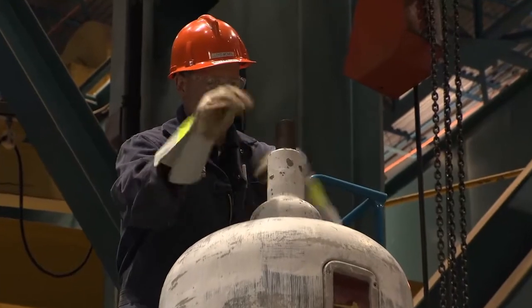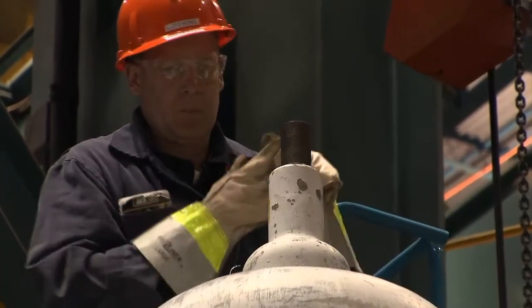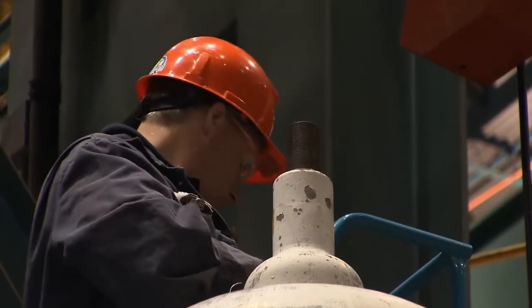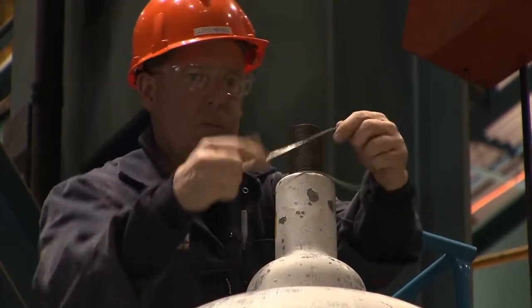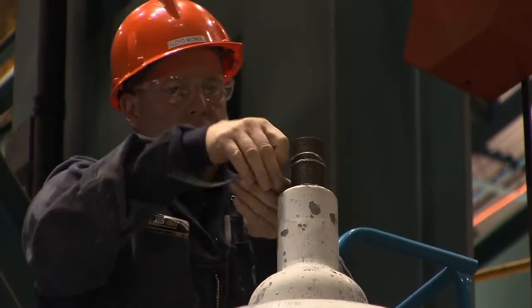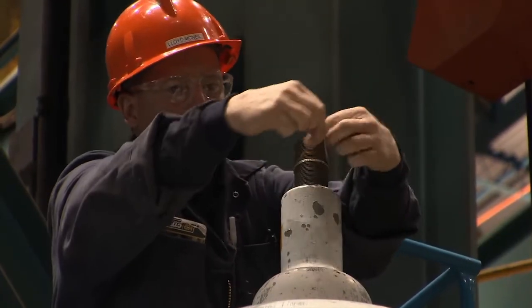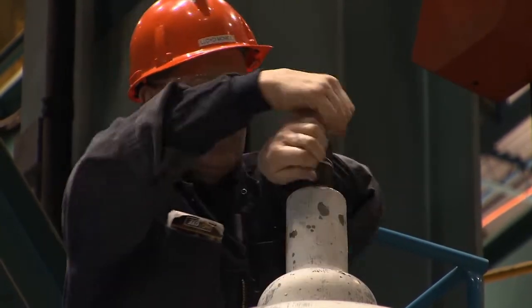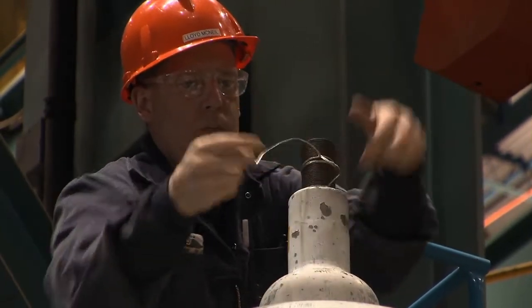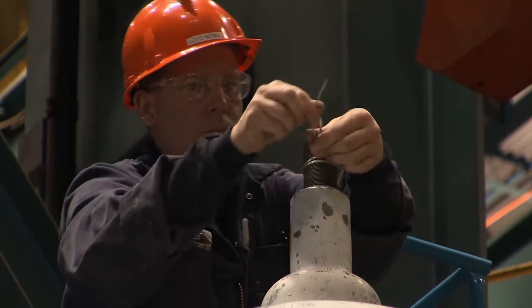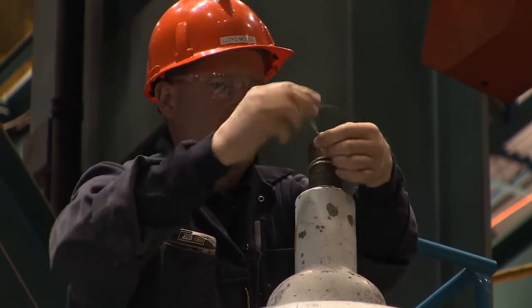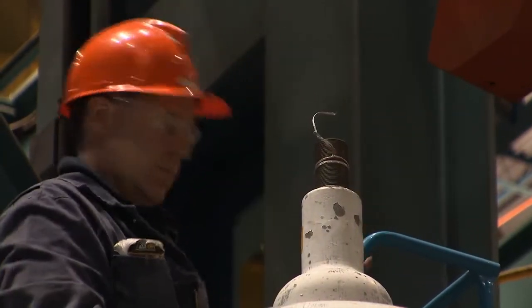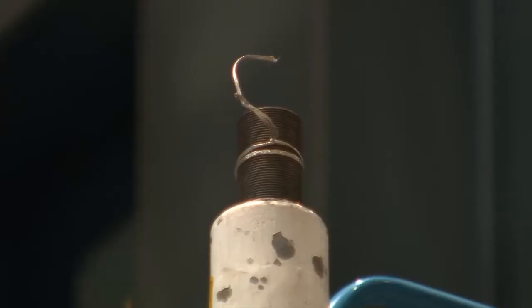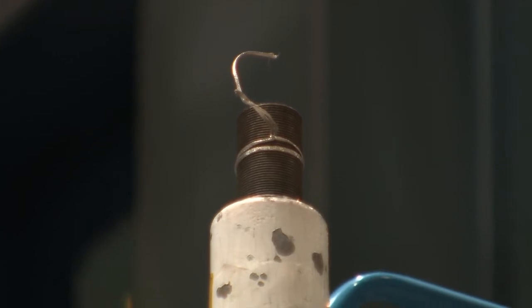To facilitate adequate transmission, a strand of 1/8 inch bare copper conductor should be tied to the threaded rod extending out from the top of the terminal on the bushing. Loop a section of strand around the rod twice, and then twist tie the ends together so that a connection clamp can easily be attached. The flexibility of concentrically stranded bare copper conductor makes it very suitable for uninsulated electrical connections.